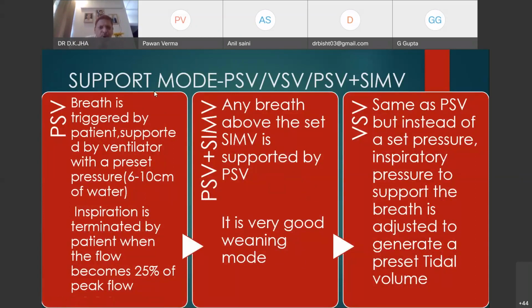It is clear. Support mode will be in the form of pressure support, volume support, or a combination of pressure support plus SIMV. SIMV I will describe in detail. This is the most frequently used term in ventilators, and in the next few slides I will describe what it is. For now, in pressure support ventilation, breath is triggered. I will describe what a trigger is. Just know that triggered means initiated. So breath is triggered by the patient, supported by the ventilator with a preset pressure like 6 to 10 centimeter of water.